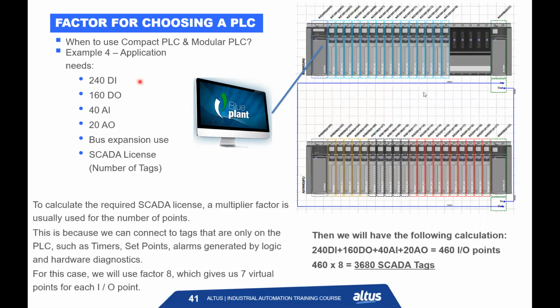I/O. And in this example, just to calculate the required SCADA license, a multiplier factor is usually used on the number of points. This is because we can connect to tags that are only in the PLC, such as timers, set points, alarms generated by logic, or hardware diagnostics. For this case, we will use the factor 8, which gives us 7 virtual points that are just inside the CPU for each I/O point that I have connected from the field to my PLC.